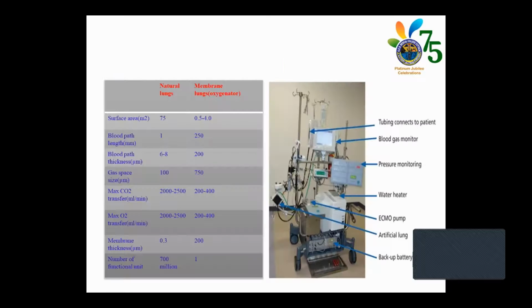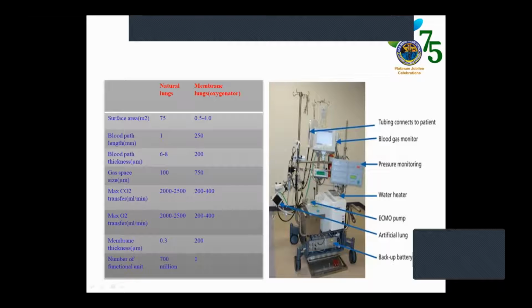This shows the difference between the natural lung and the membrane lung oxygenator, differing in surface area, blood path length, thickness, and oxygen and carbon dioxide transfer rate. On the right side is an ECMO machine, showing the membrane oxygenator and the centrifugal pump.